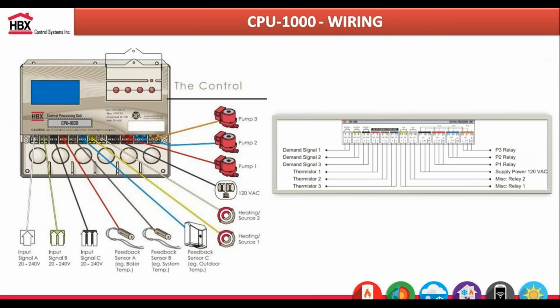You have numerous demand signals, so you can have it based off outdoor reset, or if your sensor were to go, it'll automatically go into the coldest day in terms of your demand output to your boiler. You can have different firing options with the 1000. You can have high or low fire. You can stage your boilers based off lag time, from 1 minute to 240 minutes worth of lag time.